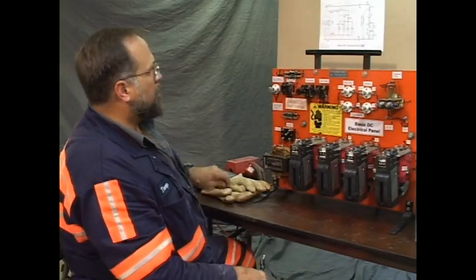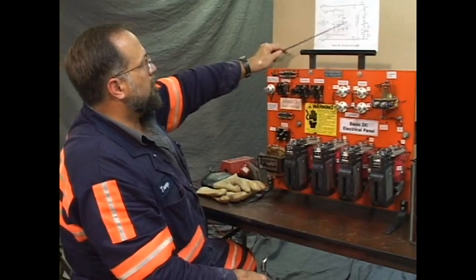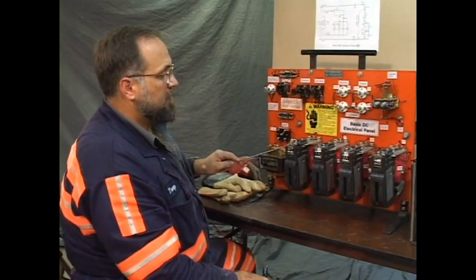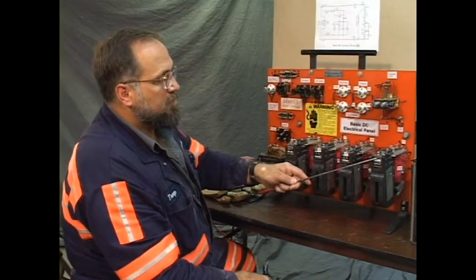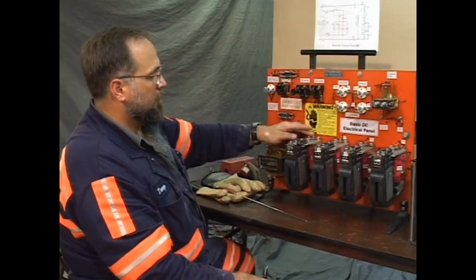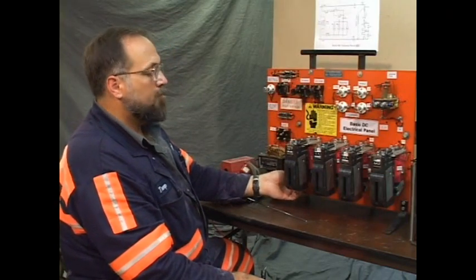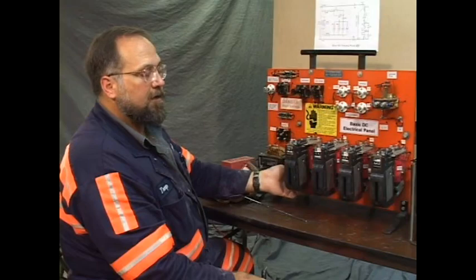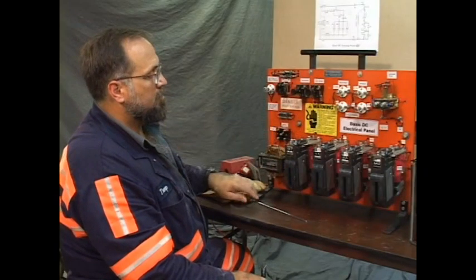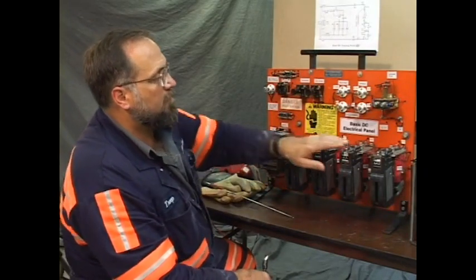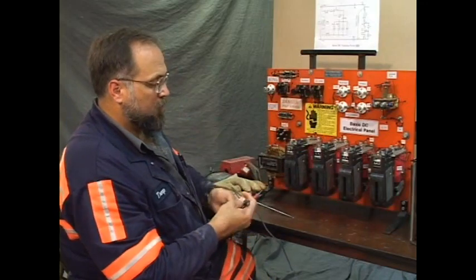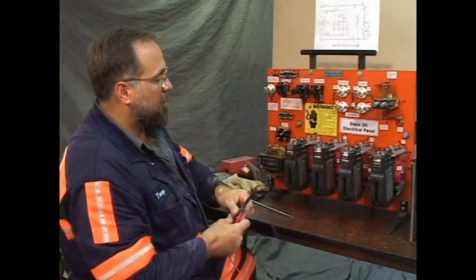Now, so far, we have checked to the line side of M1 and M2 as part of our power circuit. The line side of switchgear, both contactors and switches, is the stationary portion. The stationary part of these contactors is the top front connection. The rear connection goes to a shunt strap and goes to the movable part, the part you hear click in. That's the load side. Well, we've checked to the line sides. Now we're going to check the other side of the contactor.